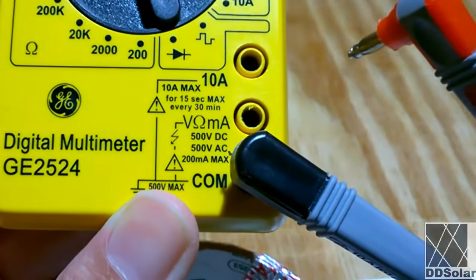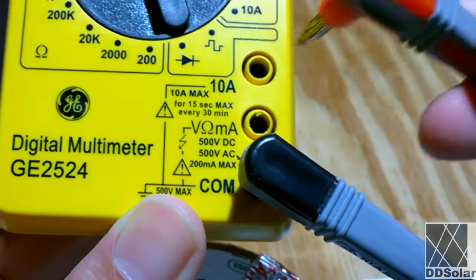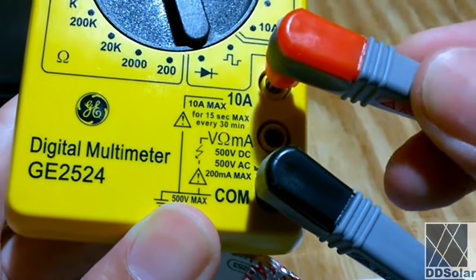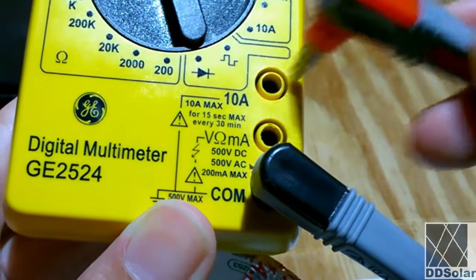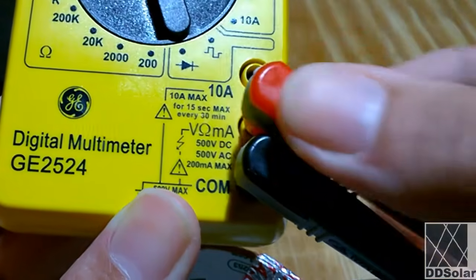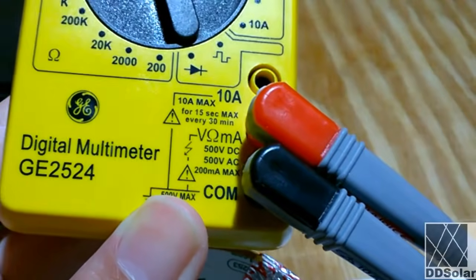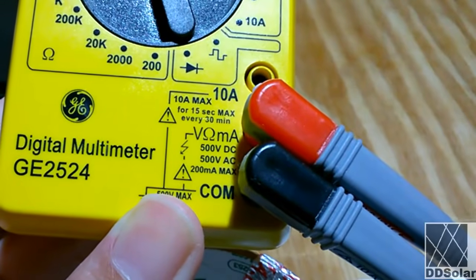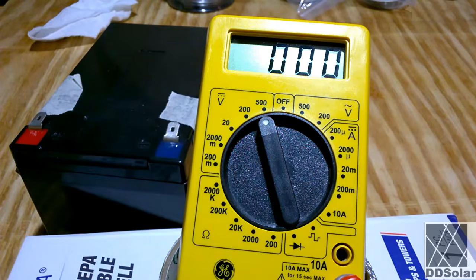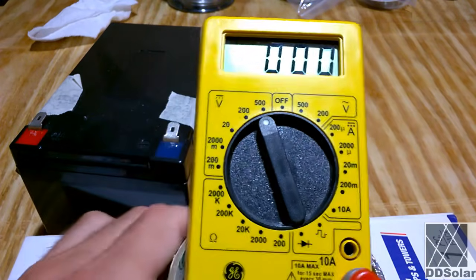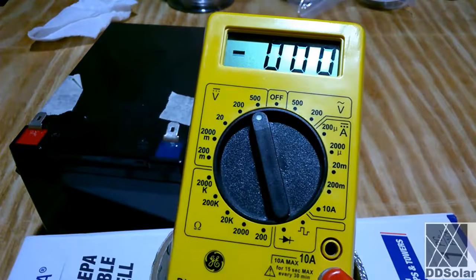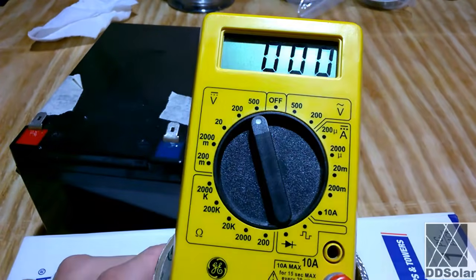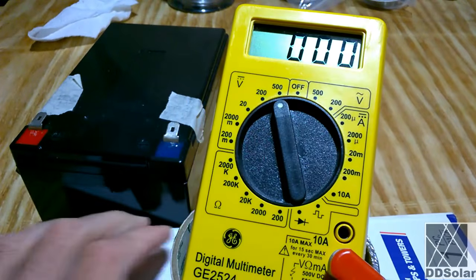Next I'm going to take my positive, and I'm going to plug it not here where it was. Originally, my two probes were plugged into these two connections here. So I'm going to plug my probe into volts, ohms, and milliamps, which is right here, which is also positive. And that will enable me to take a voltage measurement. Okay, now that we have the probes properly inserted into the meter, and not into the 10 amps connection right here, as they were when I first picked the meter up, we can go ahead and measure this battery.